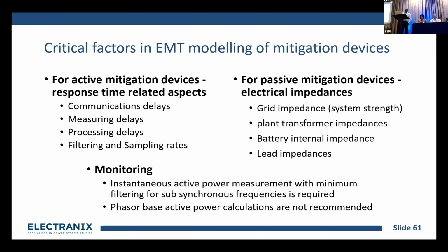In a typical BESS setup that we have seen, we usually model the DC bus as a DC voltage source, pretty much an ideal voltage source or with some impedance. So essentially, your DC bus voltage doesn't move at all. That will decouple the grid side from the load side. But if you have actual impedances, your DC bus voltage will change slightly, and that will show up on the AC side as a ripple as well. So those impedances are important to model when you are modeling passive mitigation devices.